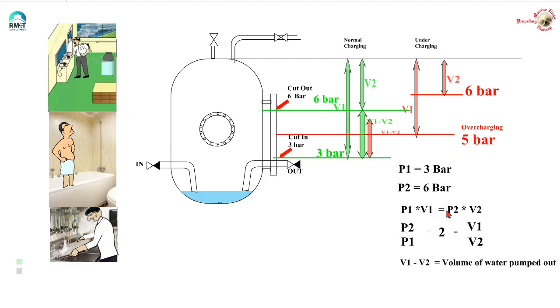We all know the gas laws. P1 V1 is equal to P2 V2. Taking the example of our particular range that is 3 bar cut in and 6 bar cut out, P1 and P2 are 3 and 6. That means P2 by P1 is equal to 2, ratio is 2. V1 by V2 is also going to be 2. And we also know that V1 minus V2, the volume of water pumped out. That means as I increase the level of water in the hydrophore and adjust the cut in pressure, the value V1 minus V2 is going to be lesser and lesser. Meaning which the pump is going to cut in, cut out more often and we are going to damage the pump. In other words, the ratio goes on decreasing and thus increase the short cycling of the pump.